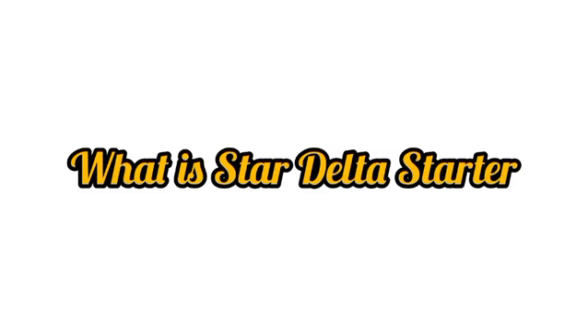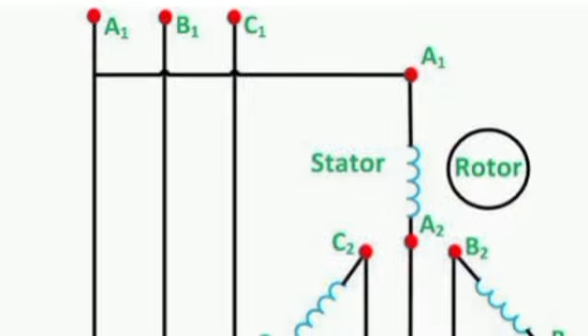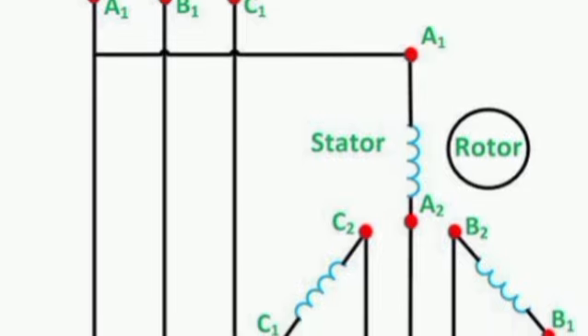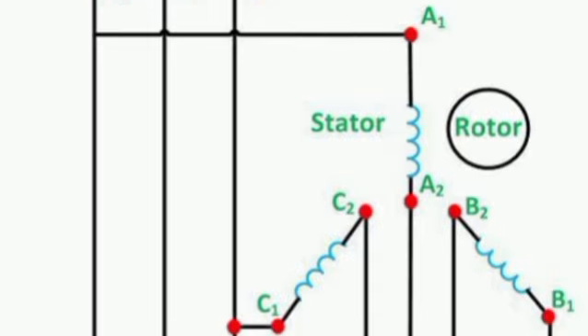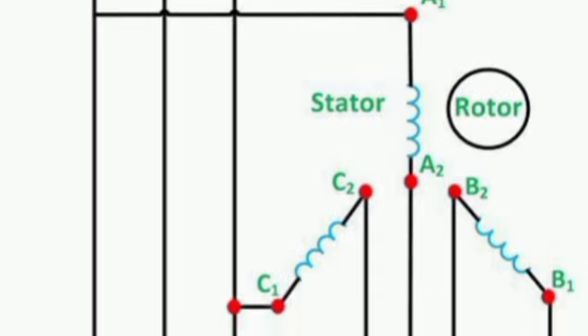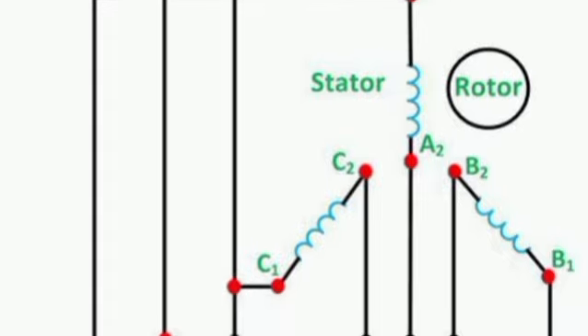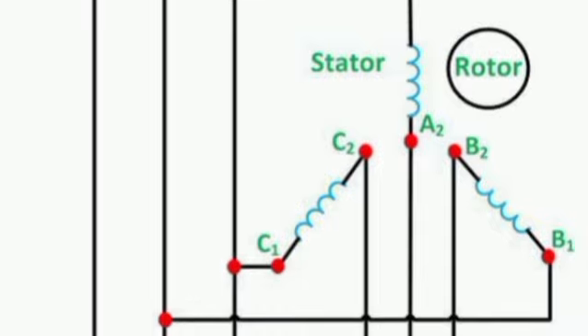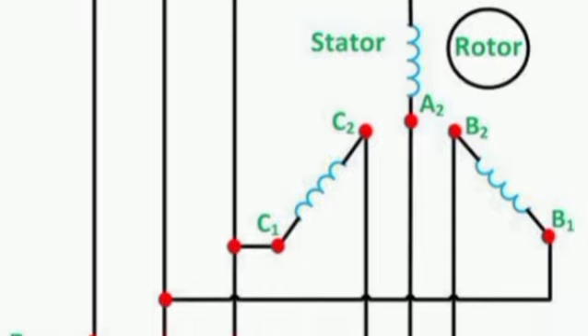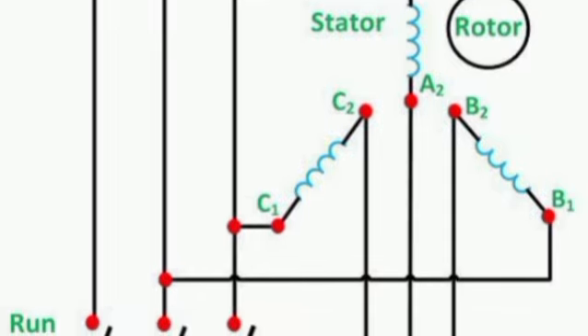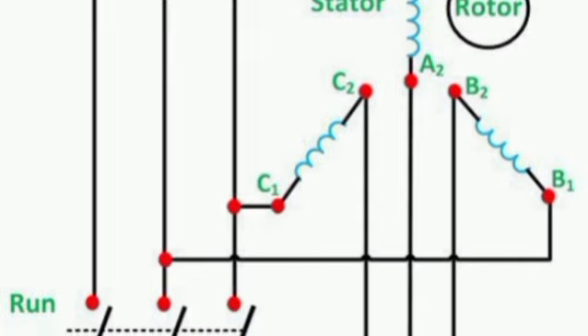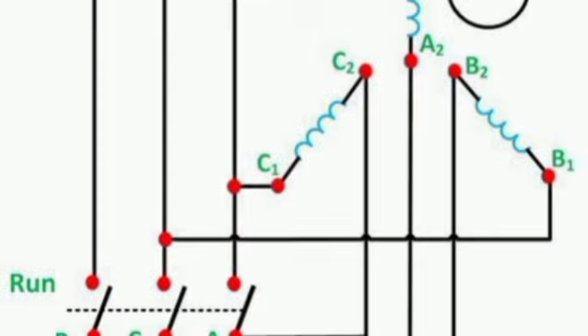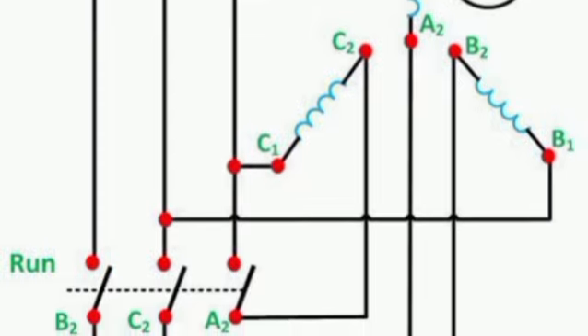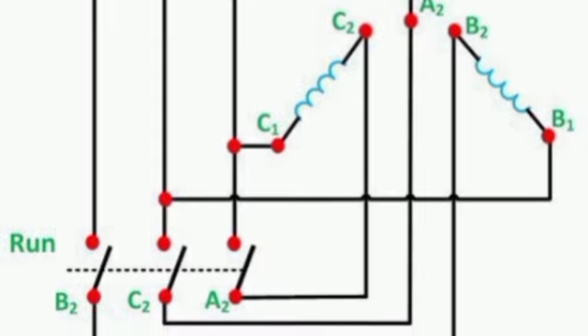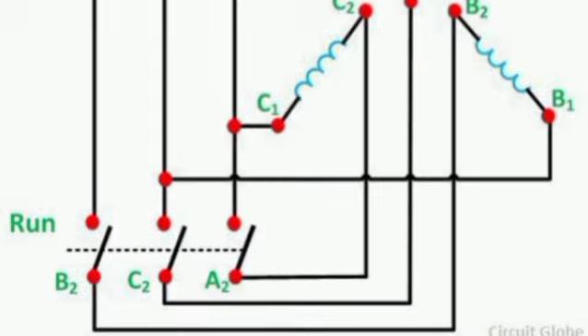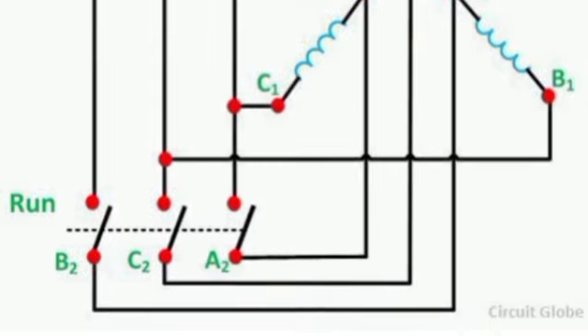What is star delta starter? Think of it as a reduced voltage motor starting method. It initially connects the motor windings in star configuration to lower starting current and then shifts to delta configuration for normal running. The function of star delta starter is to limit inrush current while still allowing the motor to reach rated speed smoothly. This method protects both the motor and the power supply network. Engineers choose this system because of its simplicity and reliability. In simple terms, it provides a balanced solution between direct online starting and more advanced electronic soft starting systems.